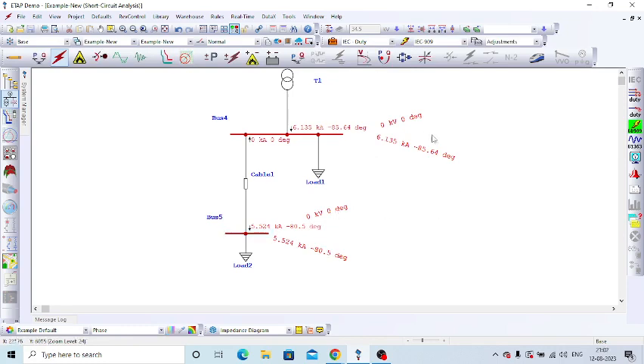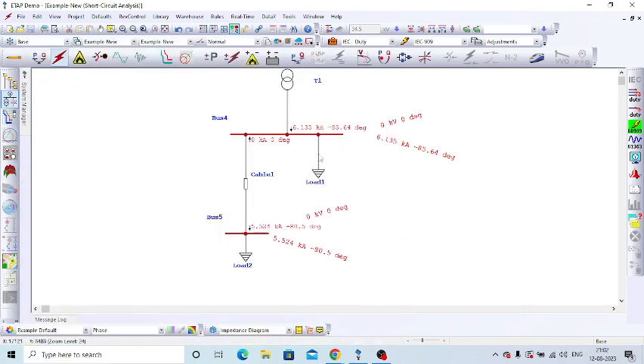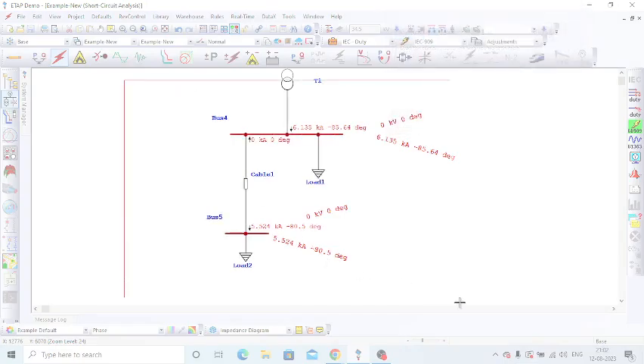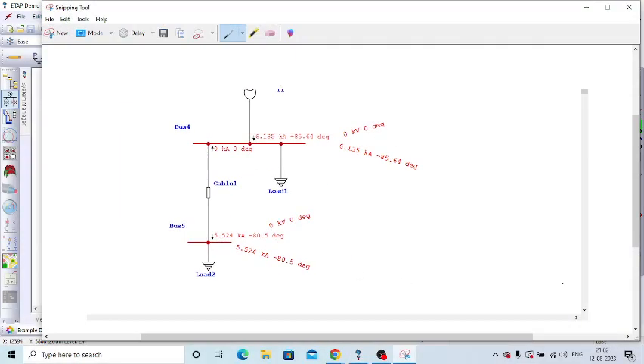IEC 60909. Can you see in this bus 4 the fault magnitude is 6.135 kiloampere, but in bus 5 it is 5.524 kiloampere. So the fault current magnitude is reduced because of the impedance offered by the cable. Okay, so in the cable selection also, there are some requirements. So how to select the cable? For the cable selection, there are multiple criteria. So one of the criteria is fault current.